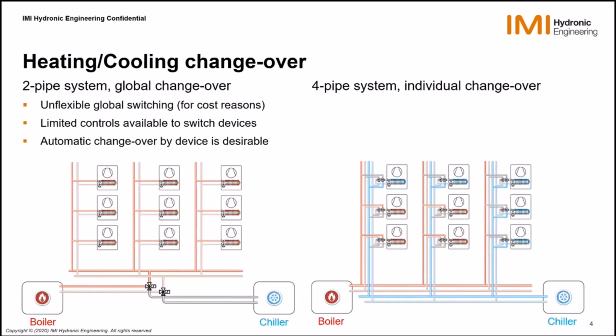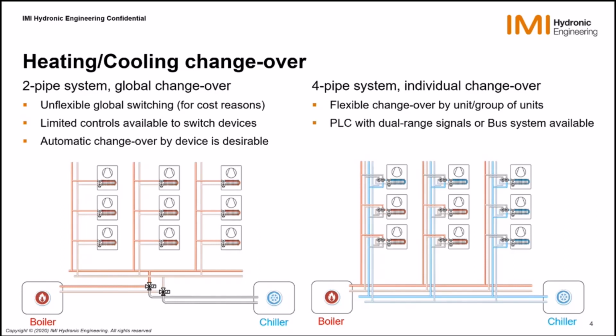Then we have a four-pipe system with individual changeover, and nowadays, in most cases, on terminal units, we would speak about a six-way valve. So we get a flexible changeover by unit or by group of units. Even when using six-way valve in office typical applications, you would have one six-way valve for a group of radiant ceilings, for instance. So it's not necessary for one module at a time, it can be for a little group of them. You would have a PLC with dual range signals or a bus system available to be able, of course, to control individually these different units. And therefore, you need to have the capability from the device to adapt itself to the chosen switching system. So this is a little bit what we have in front of us.